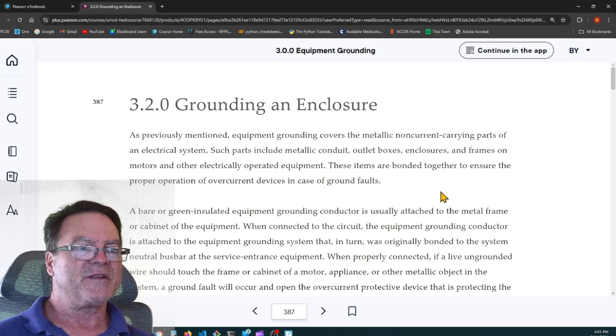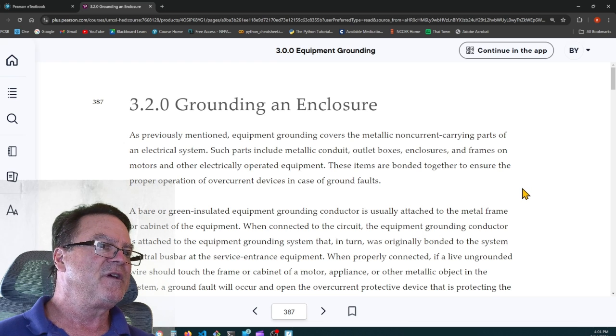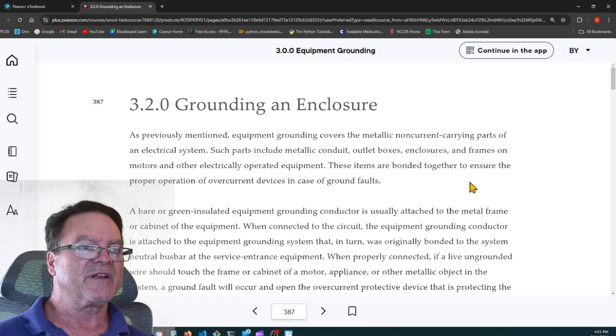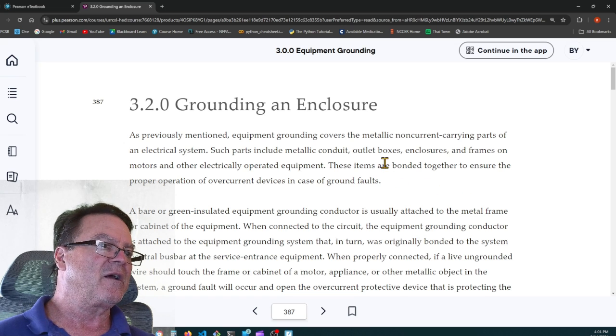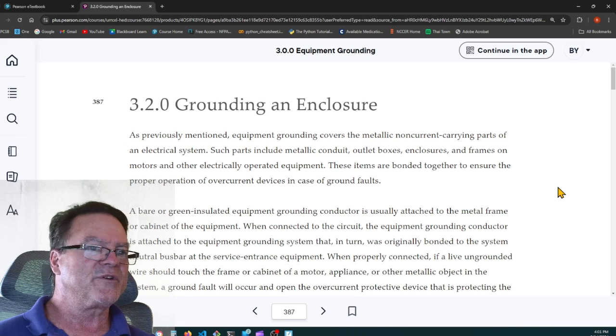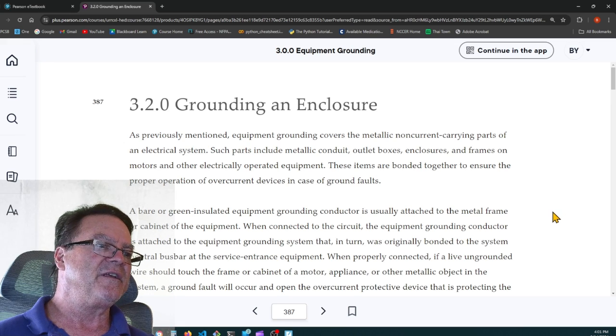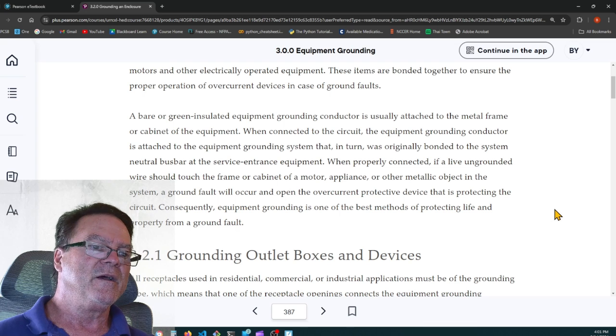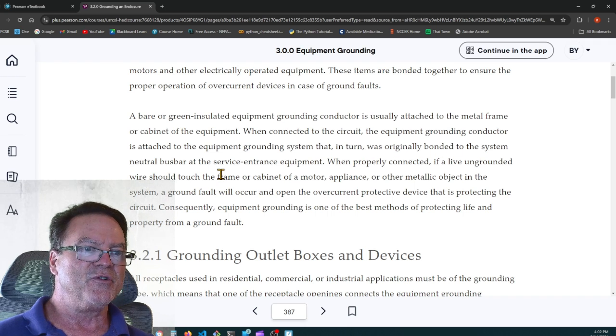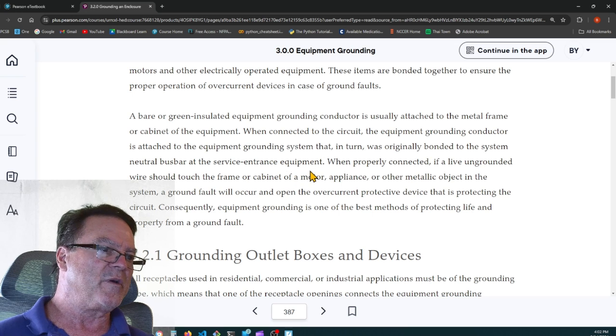3.2.0 Grounding an enclosure. As previously mentioned, equipment grounding covers the metallic non-current carrying parts of an electrical system. Such parts include metallic conduit, outlet boxes, enclosures, and frames on motors and other electrically operated equipment. These items are bonded together to ensure the proper operation of the overcurrent device in case of ground faults. A bare or green insulated equipment grounding conductor is usually attached to the metal frame or cabinet of the equipment. When connected to the circuit, the equipment grounding conductor is attached to the equipment grounding system that, in turn, was originally bonded to the system neutral bus bar at the service entrance equipment.